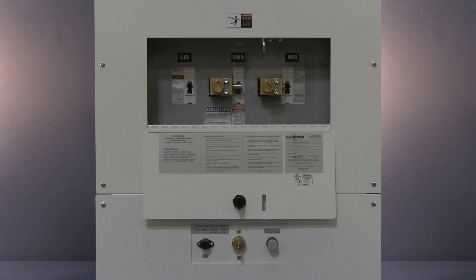There are three breakers in the top section. They are labeled UIB, which is the UPS input breaker; MBB, which is the maintenance bypass breaker; and MIB, which is the maintenance isolation breaker. There is also an Kirk key lock with illuminated push button in the bottom section.